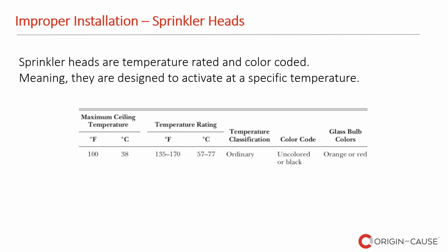So when it comes to sprinkler heads, when they're improperly installed, they can be, for instance, installed with a temperature rating that is not appropriate for that application. So if you install a sprinkler head that's supposed to be for a bedroom in a commercial kitchen, so in a restaurant, then it's possible that it's going to activate because the heat from the kitchen is rising to the ceiling level and it's going to accumulate there and possibly activate it.